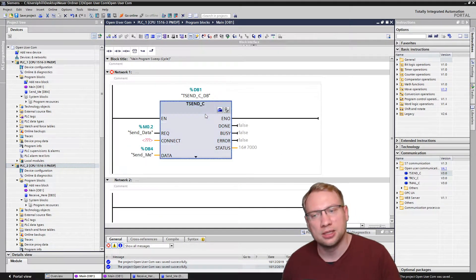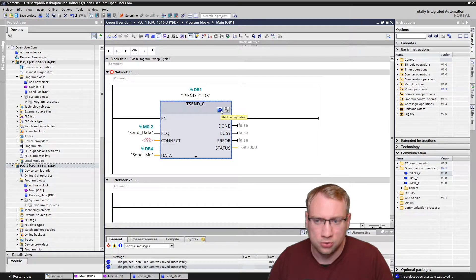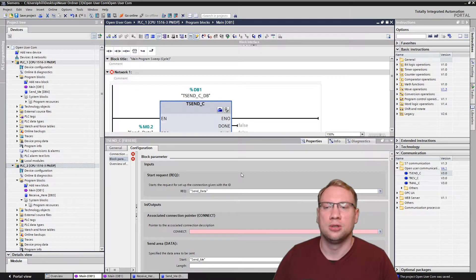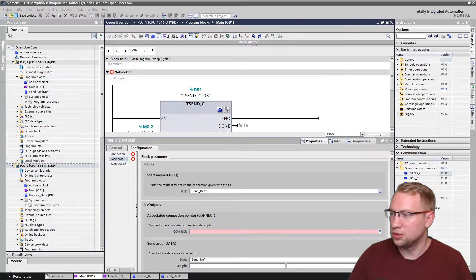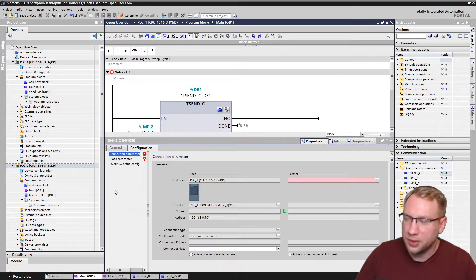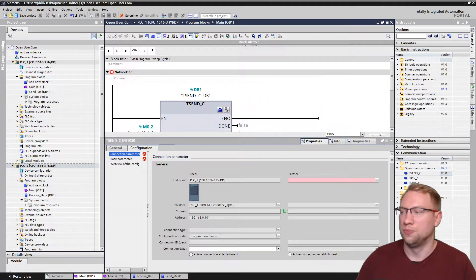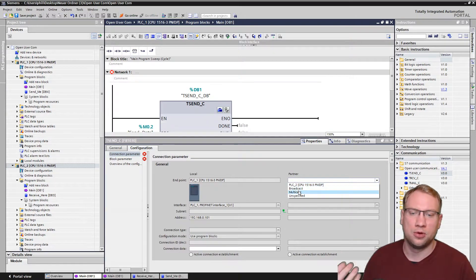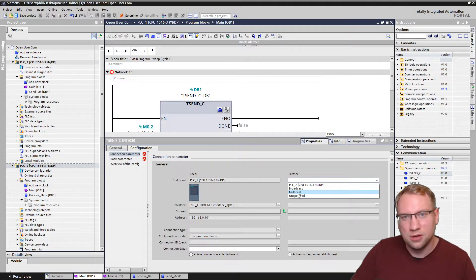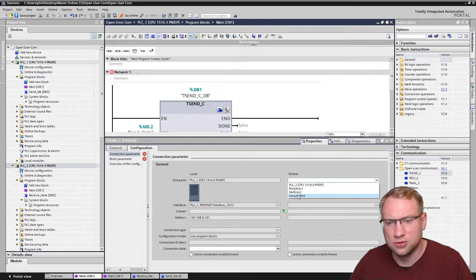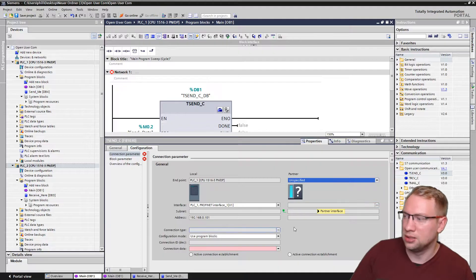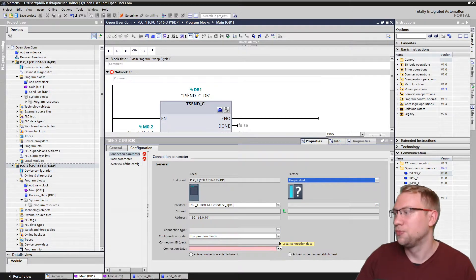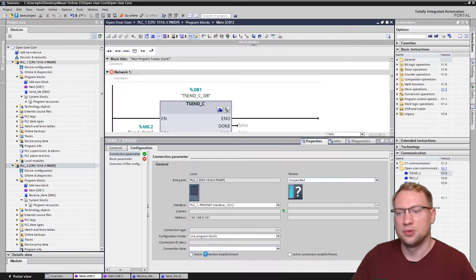The last thing that we need to tell this block, who is the partner PLC? And this we can do here on this little toolbox here on the top. You click on the toolbox. Down in our window here, in our configuration window, there is the configuration for this block. Let me push myself back into the corner here, where I belong. And there we have connection. We need to establish the connection. We need to tell this block, hey, where do you send the data to? We could now, in partner, choose the PLC that we have in our project. The other PLC, we could make broadcast, multicast. I've explained that in previous videos. Not too much in detail, but we don't need those right now. I want it unspecified, which could be anything. It could be a PC, a PLC, anything that has an IP address.